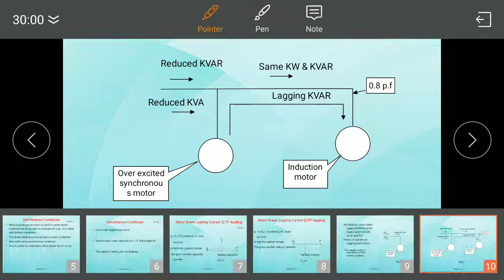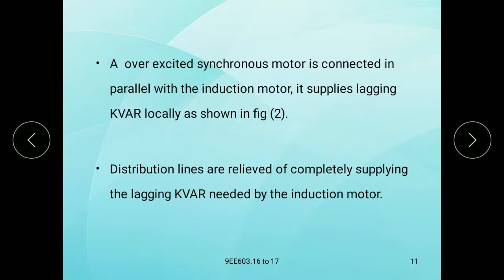An overexcited synchronous motor is connected in parallel with the induction motor. It supplies lagging KVAR locally as shown in figure 2. The distribution lines are relieved of completely supplying the lagging KVAR needed by the induction motor. So now the supply lines have to handle reduced KVA and reduced current.